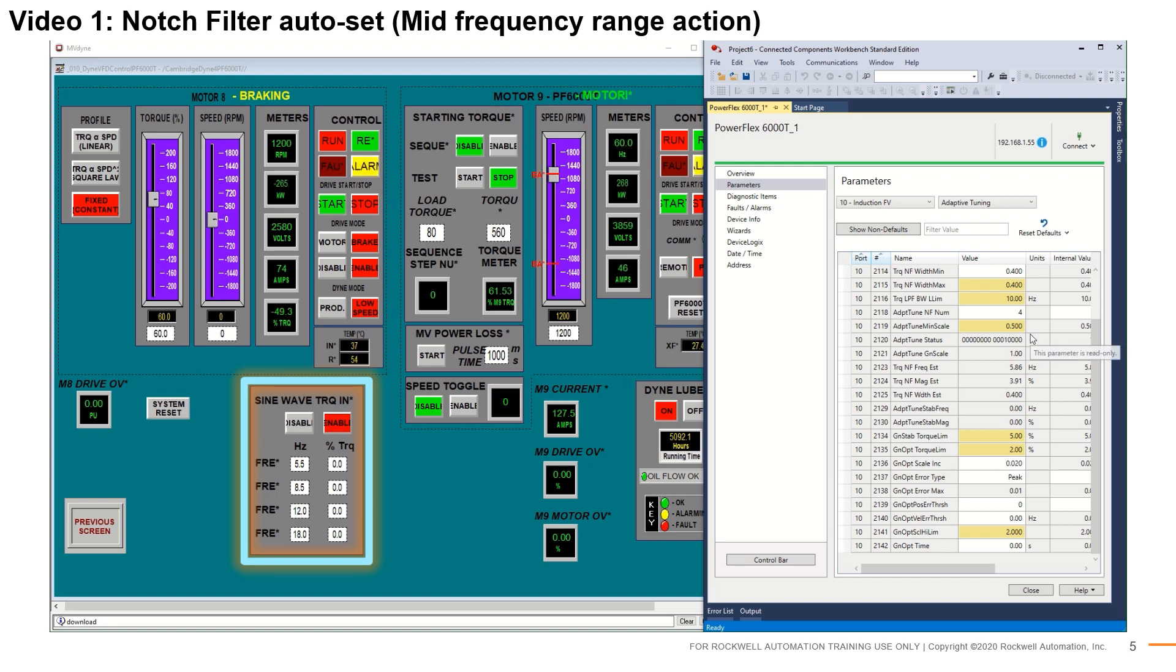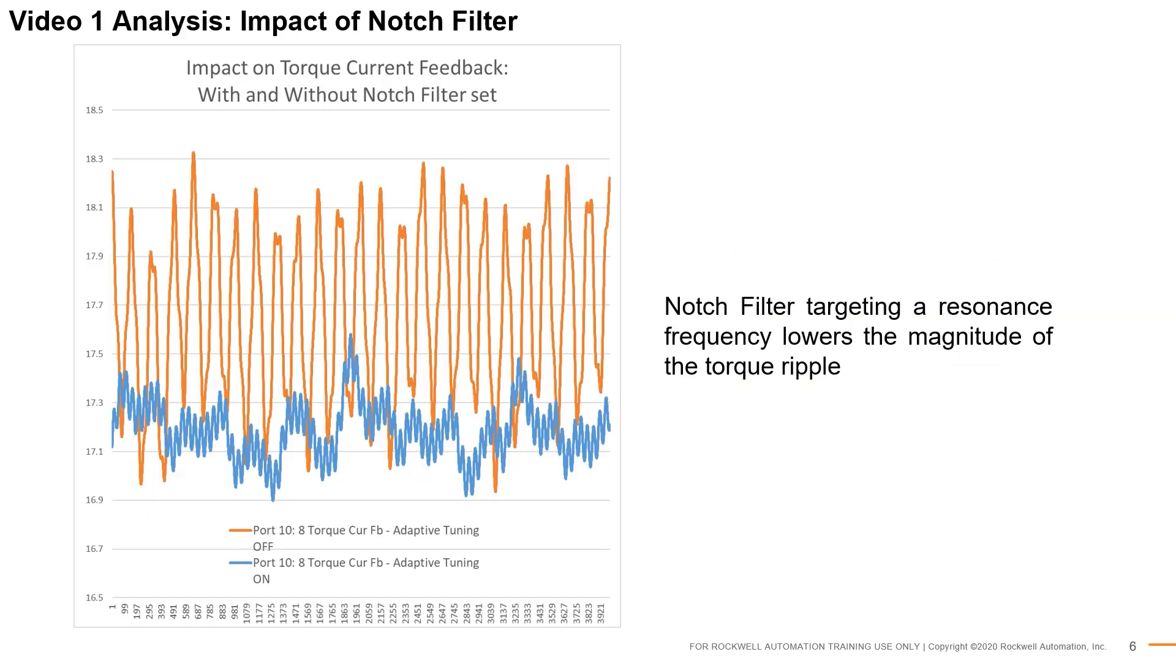Let us now review the impact of setting a notch filter targeting a resonance frequency. We can observe the impact of the notch filter. In this example, a 6 Hz sinusoidal load is constantly injected. The orange trace shows the torque current feedback when the load is applied and notch filtering is inactive.